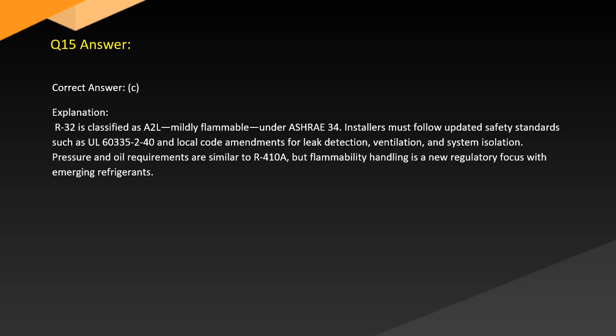Answer. Correct answer: C. Explanation. R32 is classified as mildly flammable under ASHRAE 34. Installers must follow updated safety standards such as IEC 60335-2-40 and local code amendments for leak detection, ventilation, and system isolation. Pressure and oil requirements are similar to R410A, but flammability handling is a new regulatory focus with emerging refrigerants.